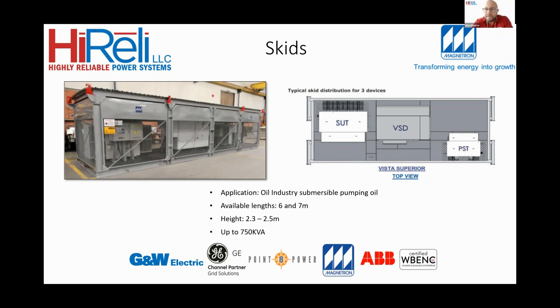And then for any harmonics or any power quality issues you might have, you have your phase shift transformer to clear that out. So while Magnetron can do the step up and the phase shift, they do not do the variable speed, but they can procure that, put all 3 onto a skid for you and ship it out to site where it'll be above ground for oil pumping. Available lengths 6 and 7 meters, heights 2.3 to 2.5 meters, and then they do this up to 750 kVA rated.